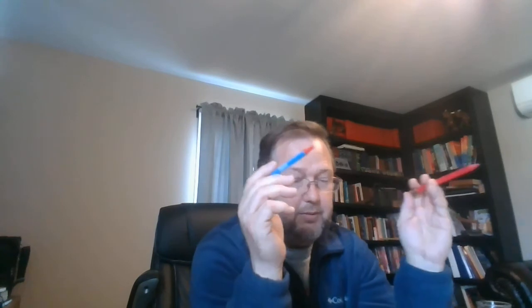So what's most likely happened is, if you pull that disconnect and look at the lugs inside, one of them's burnt or something's happened there. Something internally on that disconnect is bad. But you need to understand your L1 and L2 is what we're dealing with here. There needs to be 240 volts there total, because there's a 120 volt difference between the two. The sum of that is 240.